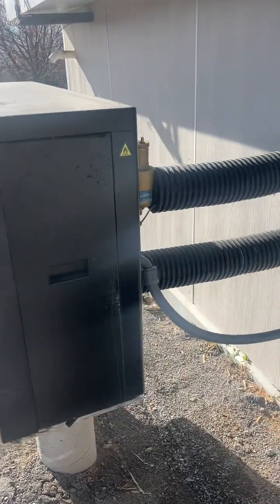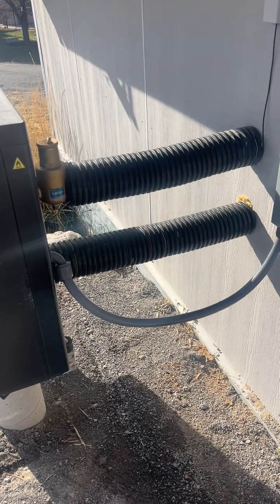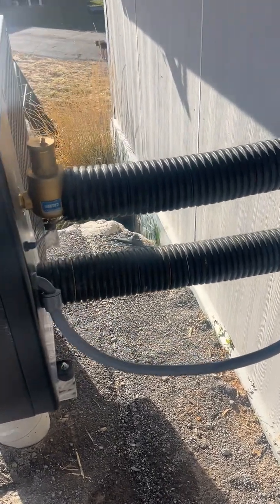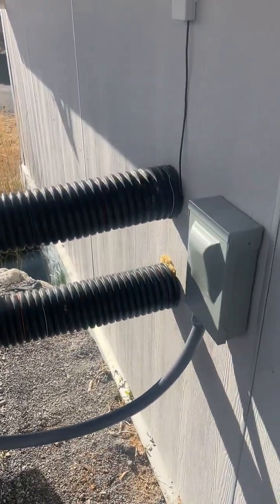When I came off the back, I used some Watts Radiant Onix 1-inch tubing — rubber tubing — so that gives me my vibration isolation and also was a simple way to get from the back of the unit into the building.